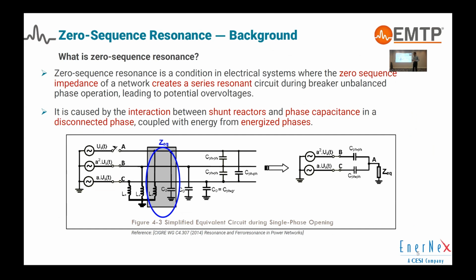So for example, if you see in this circuit, we have a source, and then there's an unbalanced circuit breaker operation. One of the phases is open, whereas the other two phases are closed. There is a shunt reactor, and the phase to phase capacitance and phase to ground capacitance of the lines. Its equivalent resonance circuit would look like this. So phases B and C, the healthy phases, and then the phase to phase capacitances, and Z equivalent, which is basically the shunt reactor and the phase capacitance.